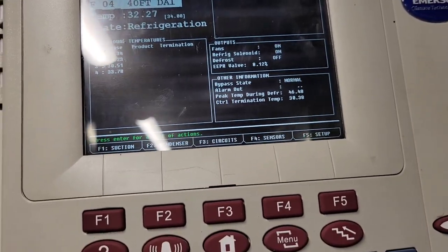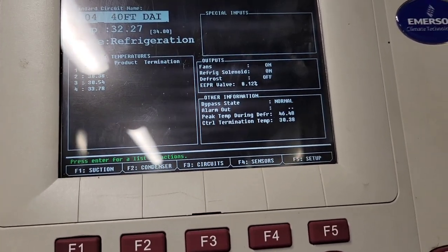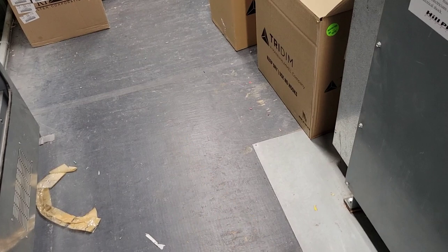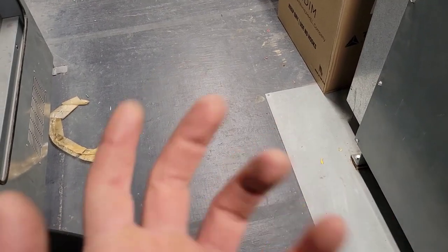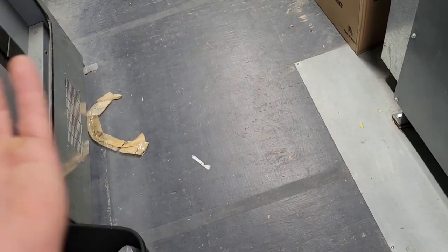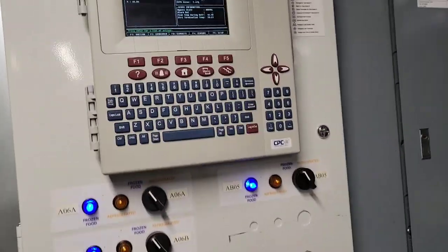33, yeah, 1.5 degrees. I want it to be around 33. So a lot of people, they do 32. 32 is fine to do because remember, ice is 32 degrees. And then you put it in water, and the water will come down to the temperature of the ice, which is around 32 degrees. But you got this whole question of what materials were in the ice. If you have a little bit of salt in the ice, it's really 31. If you have more hard materials in the ice, it could be 33. So I just do 33. 33 is good. And most things don't get harmed by being a little bit colder.